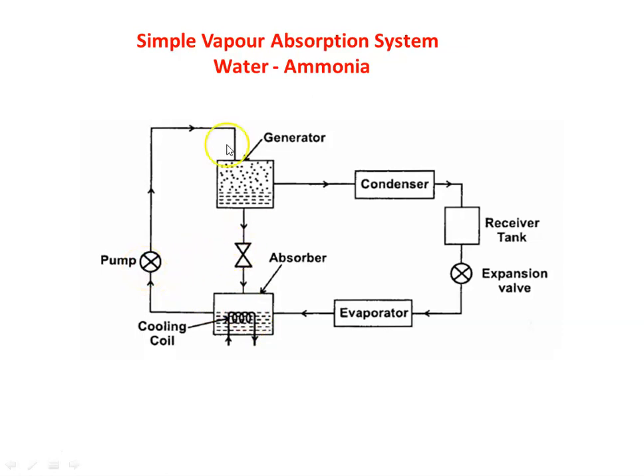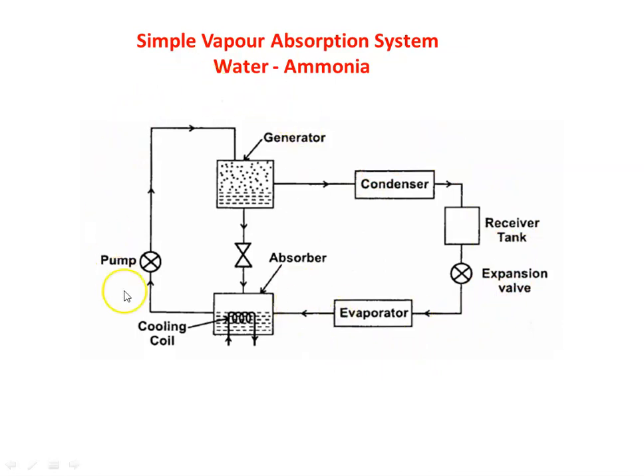If you compare the simple vapor absorption system with the vapor compression system, the condenser, receiver tank, expansion valve, and evaporator are common components. The compressor in the vapor compression system is replaced by three other components: the generator, absorber, and pump.